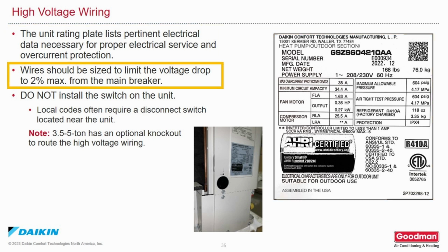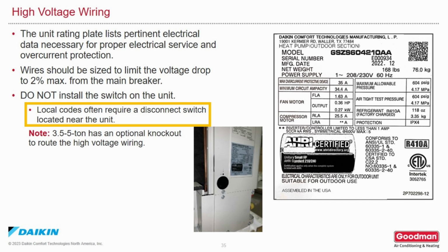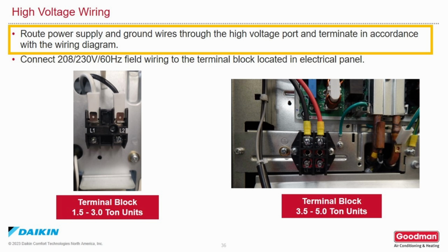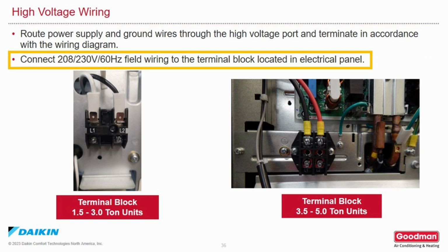Wires should be sized to limit the voltage drop to a 2% maximum from the main breaker. Do not install a disconnect switch on the outdoor unit, although local code may require a disconnect switch be located near the outdoor unit. 3.5 to 5 ton outdoor units have an optional knockout to route high voltage wiring through. Route power supply and ground wires through the high voltage port and terminate in accordance with the wiring diagram. Connect 208/230 single phase field wiring to the terminal block located in the electrical panel.